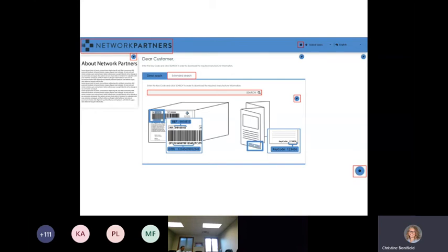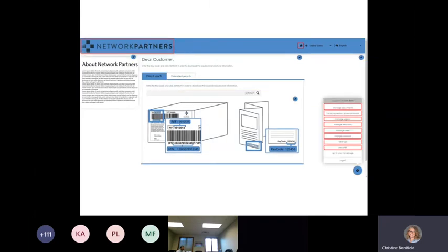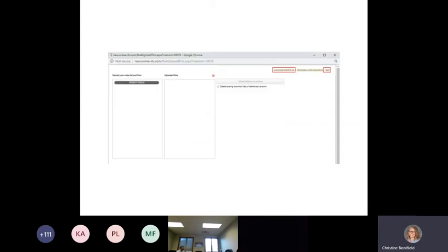The backside of this website is where you load and maintain your eIFU PDFs, your documents, and product metadata, and where you link the associated SKUs and documents. Here's where you would upload your eIFUs and document metadata. You might want to consider a file naming convention that works for both your doc control as well as your eIFU website. You would also associate the revision number, publish date, and approval date of the eIFU in this metadata.